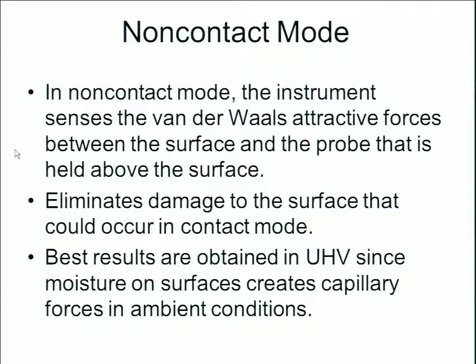In non-contact mode, the instrument senses van der Waals attractive forces between the surface and the probe, which is held just above it. There is never any contact between the tip and the sample, although they are held very close. This eliminates all damage to the surface. The best results in non-contact mode are obtained in ultra-high vacuum, since we can remove the moisture that would normally create capillary forces in ambient conditions.